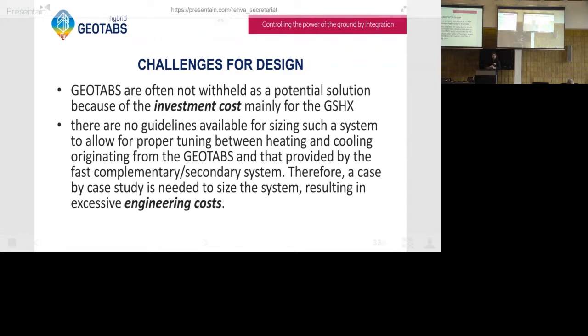First issue is that although the TABS as such are rather cheap, because they're reusing a structural element also as an emission element, for a GEOTABS concept, they are combined with a geothermal heat pump, and there the geothermal heat exchanger is a big investment. So there's a large investment cost that is later offset by a low operational cost. But in a mass market situation, it's often difficult to convince a potential or future building owner that they should invest more and that they will get that gain back, as Wim said earlier.